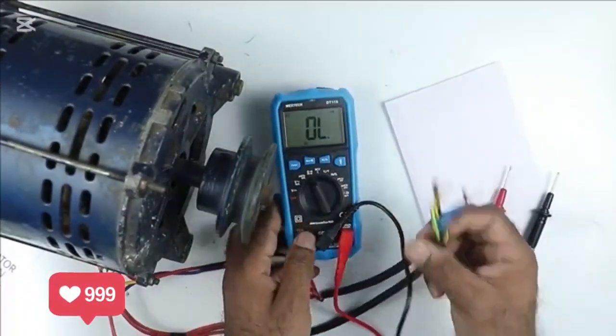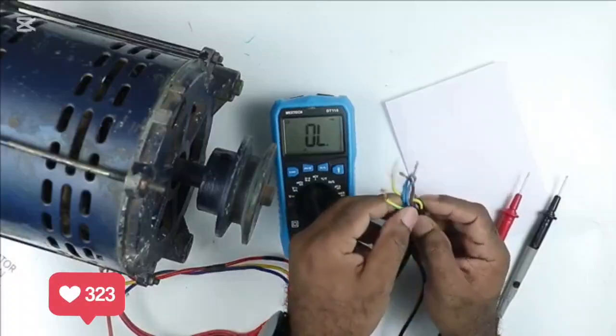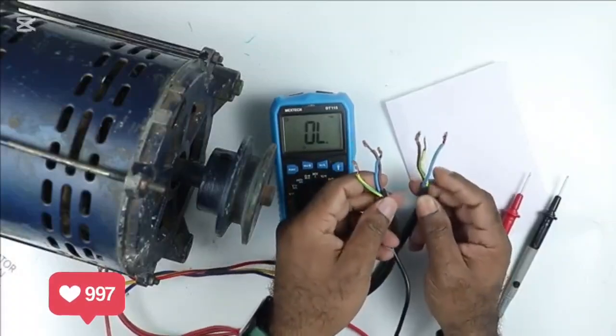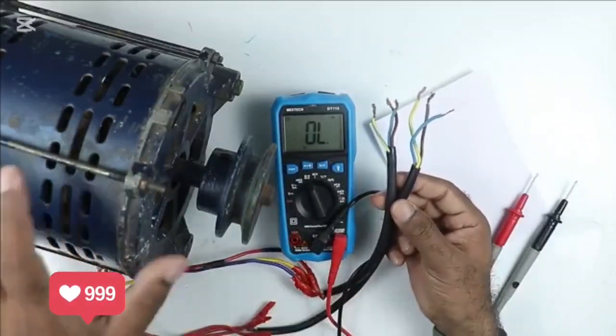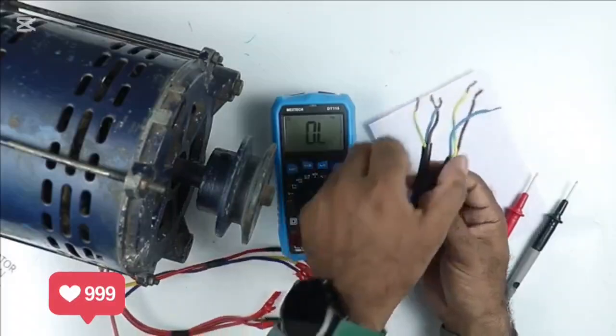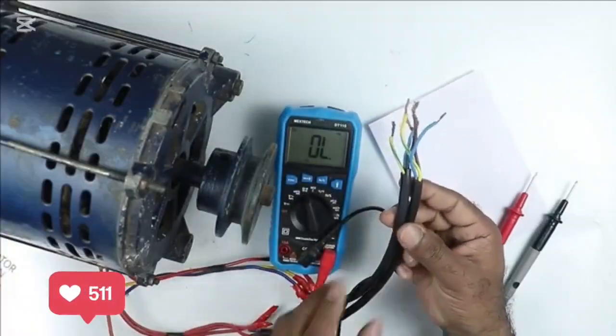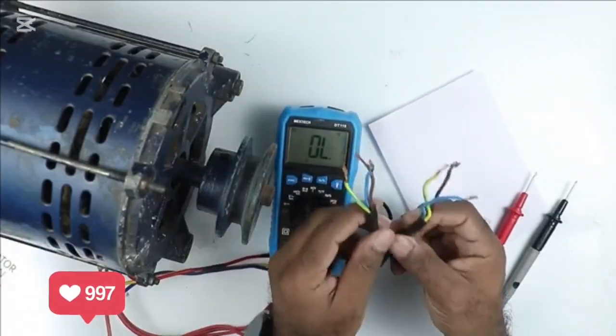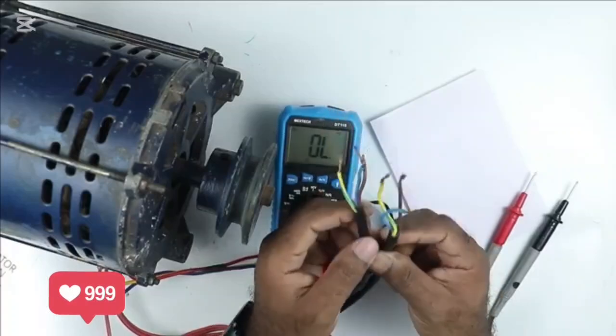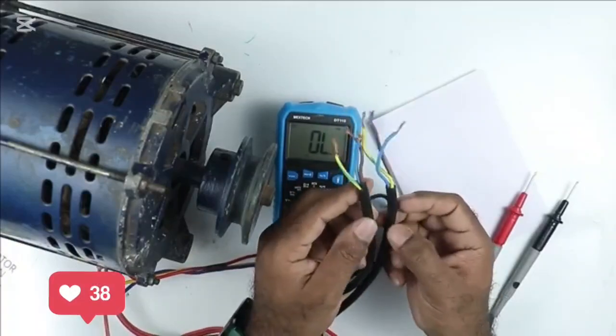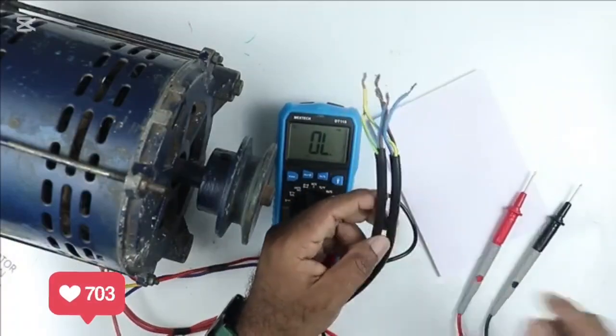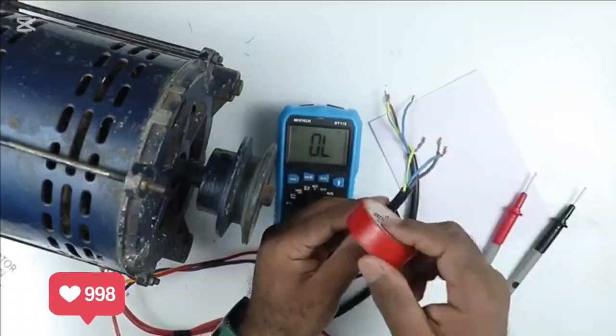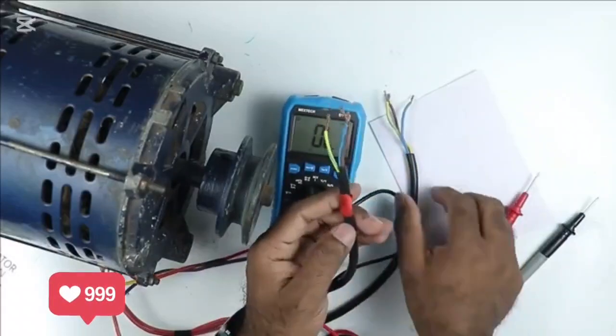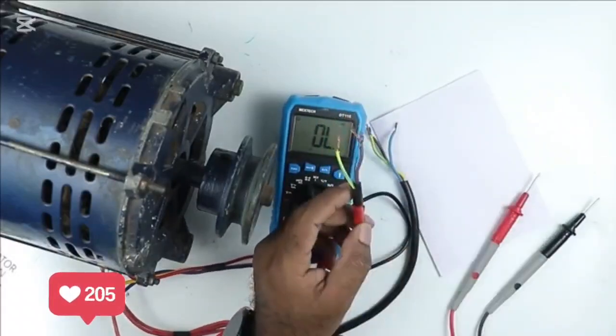These 6 wires coming out of the motor, you have to check for continuity in these wires. In these cables coming from the motor, we don't know which wire comes from where or where to connect. So to identify the wires, first put a tape on one of the cables. I put a tape on this cable. This will be the first cable, and this is the second one. Now what you have to do, listen.